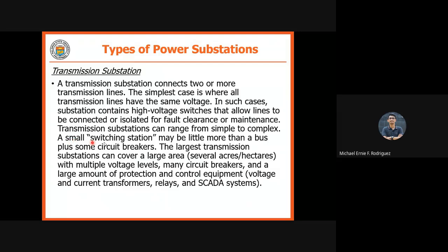So, a small switching station may be little more than a bus plus some circuit breakers. Pero pag malaki naman yung transmission substation, napakalaki naman ito. Okay? We have a large area with multiple voltage levels. So, merong 500 kilovolt, bababa niya to 230 kilovolts. Meron ding ibababa niya to 138 kilovolts depending on the next transmission line na pupuntahan niya. Okay? And then we have marami rin circuit breakers. This is because of your tawag dyan, bus scheme or bus layout. Depending on the bus layout, magkaroon tayo ng napakaraming circuit breaker.